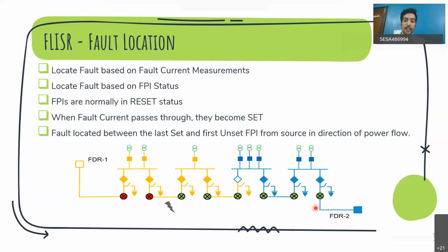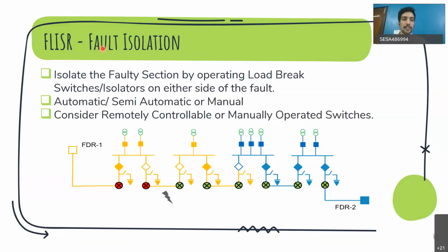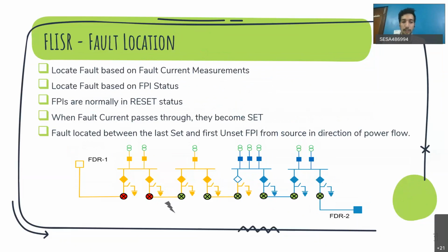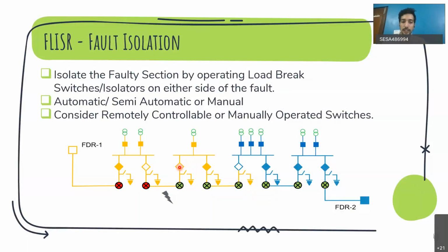So we have located the fault. The next part is isolating that fault. Now that the fault has been located, the fault isolation algorithm will run, and it will suggest the switching actions that need to be done to isolate the fault. For example, in this case, previously both of them were closed. It will suggest you to open this and open this so that the faulty section is isolated.